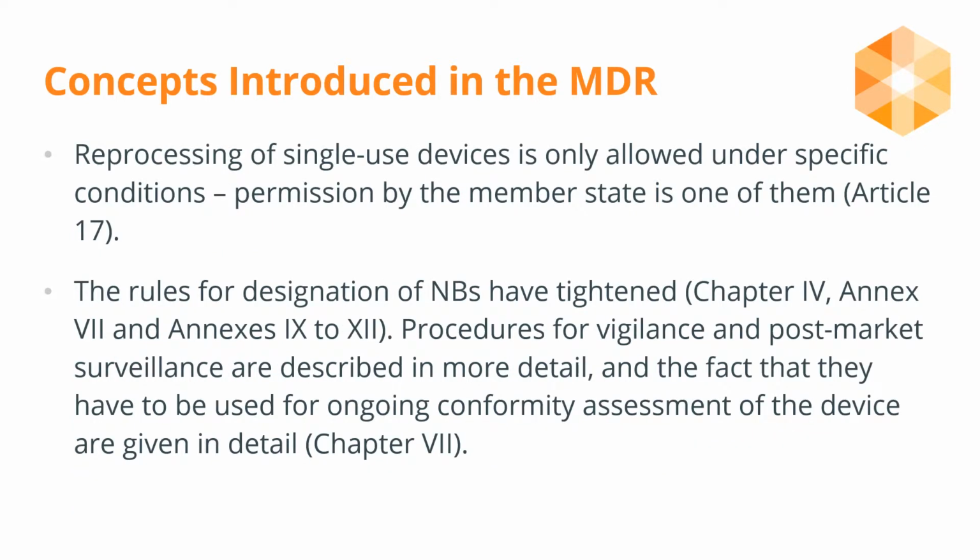Single-use device reprocessing is only allowed under specific conditions, including permission by the member state. There have been many details added to the procedures for the vigilance and post-market surveillance, and the fact that they must be used for ongoing conformity assessment of the device. Also, the rules for designation of notified bodies have tightened.